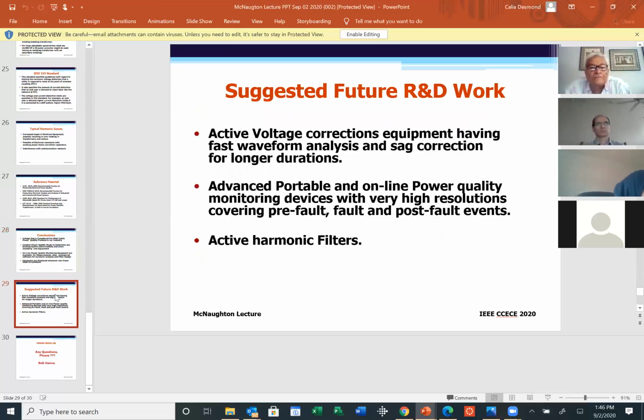I thought I'd share with any postgraduate students on the call some activities, if they are interested in taking them up as their R&D or research project. The active voltage correction equipment: if they can develop equipment with faster waveform analysis, because for this equipment to work properly, they monitor online the condition of the waveform, and within milliseconds they have to analyze that waveform and make a decision for voltage sag correction, and hopefully for a longer duration, depending on the system design they use.